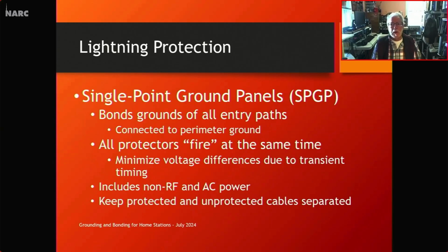When you run your cables, and we'll see a drawing of this in a minute, what's important is to keep the protected cables, which are downstream of your protected devices, together, and keep them away from the cables that might be carrying destructive transients or surges. So that when a surge occurs, you don't want that energy to jump across your protectors to where the protected cables are.